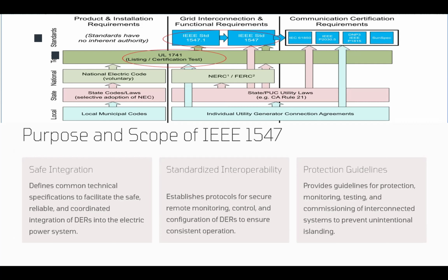Okay, now another purpose is the protection guidelines. So we wanted to protect both grid equipment and the DERs when we talk about abnormal system conditions. By specifying some monitoring and testing, or commissioning procedures, before the DER is activated, we make sure that we are protecting both grid and DER. They are also required to meet some harmonic distortion limits, or maintain the power factor within certain specified limits, or follow some voltage regulation rules. These are all for protecting the grid, customers, and the DER itself, which also includes those ride-through requirements that we are going to talk about.